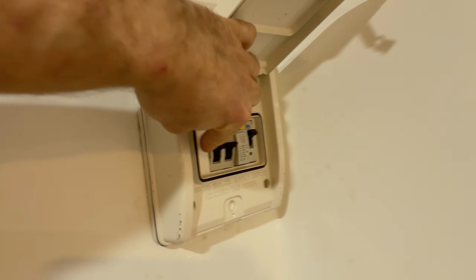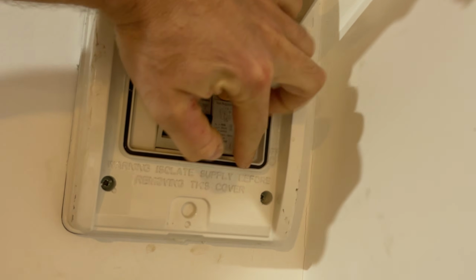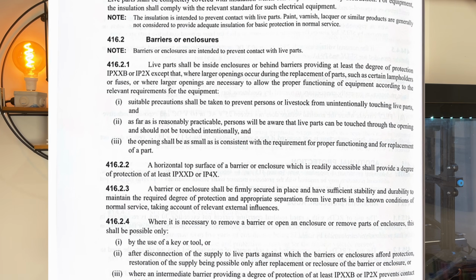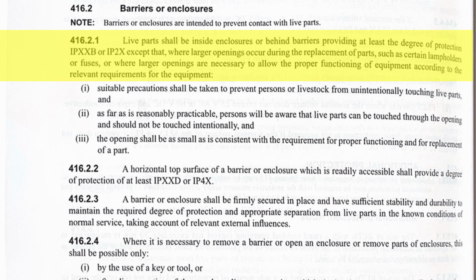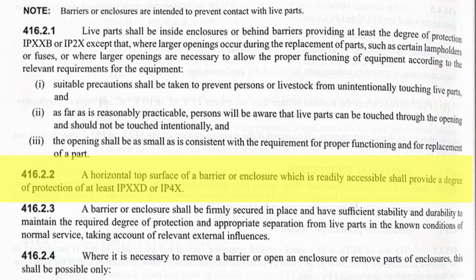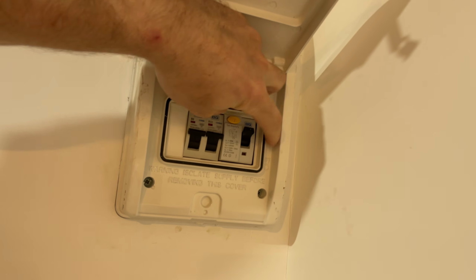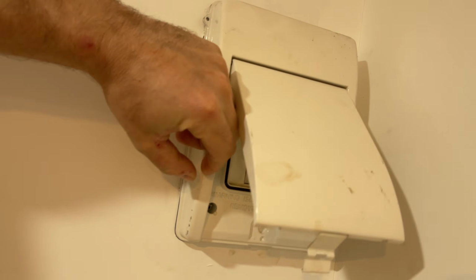That brings me nicely onto barriers and enclosures or obstacles to prevent access. Think of all the touchy bits of a consumer unit that are buried inside that consumer unit, behind screws. The same goes for sockets, corded appliances and so on. This is where our international protection codes come in. Our big book gives requirements for different levels of protection for different situations. To put meat on the bones, as it were, to our IP ratings, the regs say in 416.2.1 that enclosures are required to meet IP2X, but later on in 416.2.2 the horizontal top surface is to meet IP4X, meaning in simple terms that you wouldn't be able to get a finger in the consumer unit or a cable in the top without a tool to remove the cover. Simple, right? And it's all there for safety.